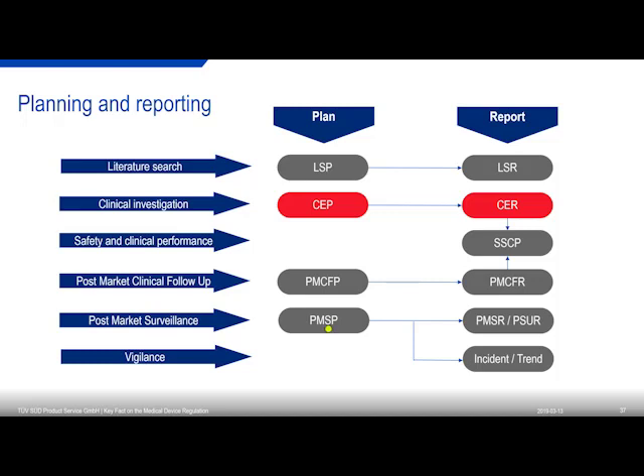Post-market surveillance is something that you actively have to do, so you have to have a post-market surveillance plan, and depending on the risk classification of the device, you will have a post-market surveillance report, or you will have a periodic safety update report, which also will have influence on your clinical evaluation and your summary on safety and clinical performance, and will therefore be requested from your clinical evaluation plan as an input. And if you have vigilance ongoing, then you might have incidents and trends. So it's not only about writing a clinical evaluation report and being fine. You have to modify your whole quality management system in order to collect, document, and plan all sources of data that you can get information out of about your device, because that is extremely important for the future.